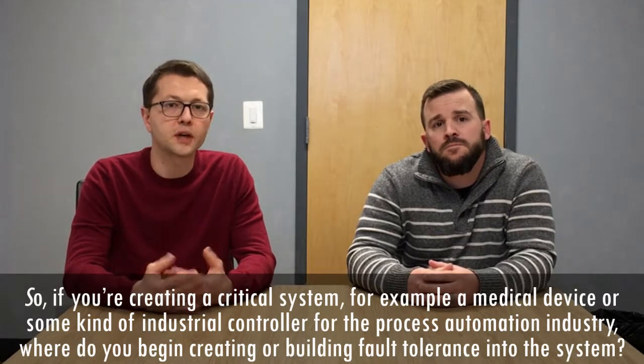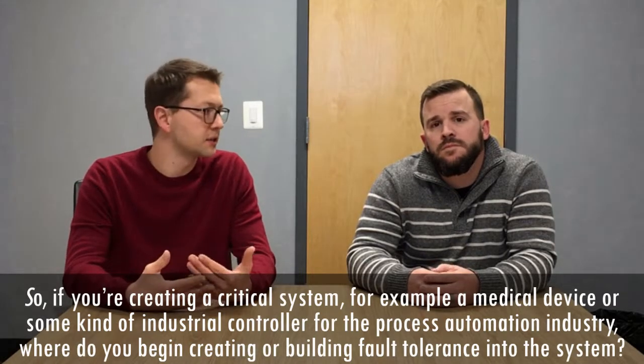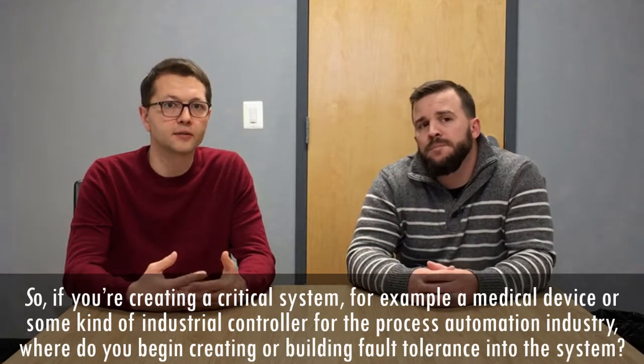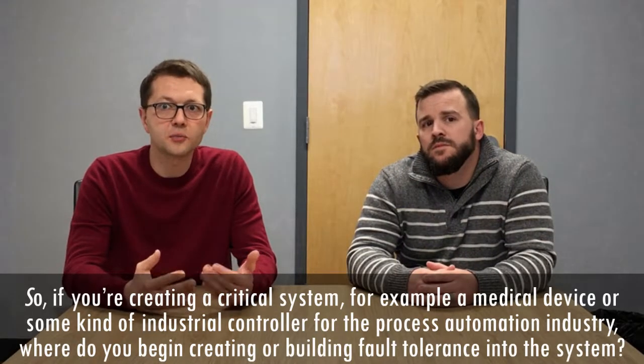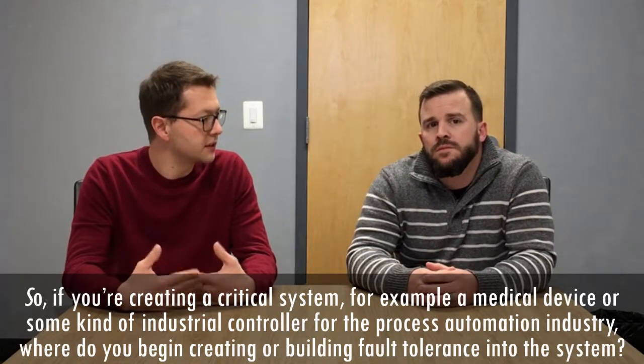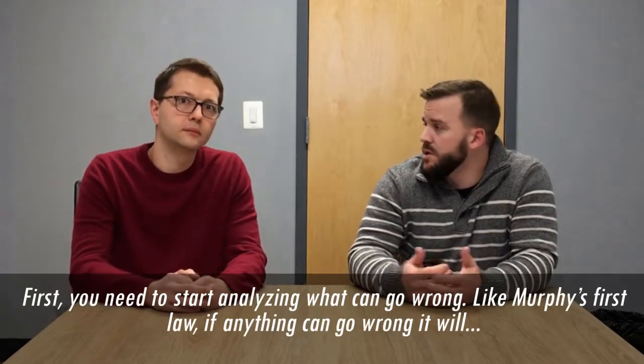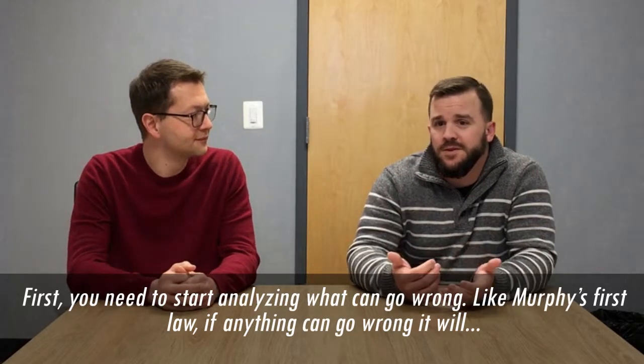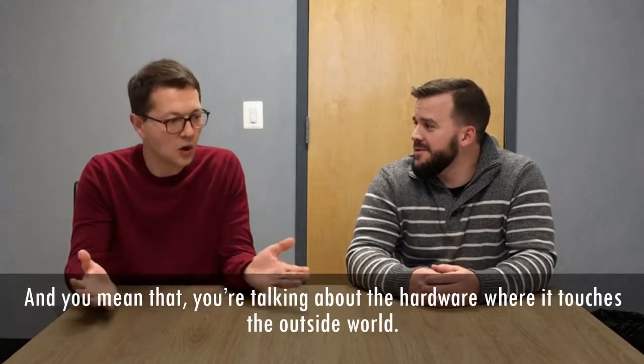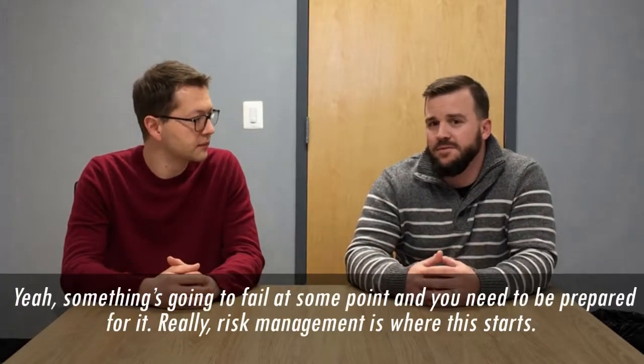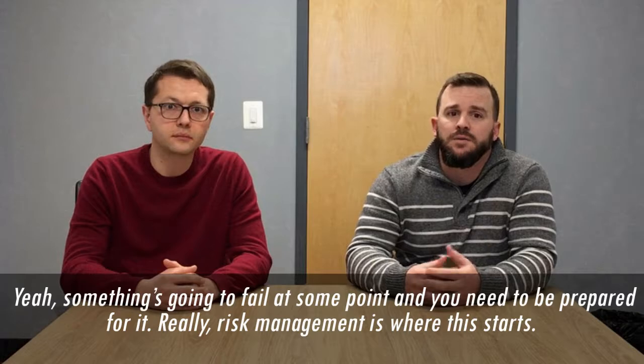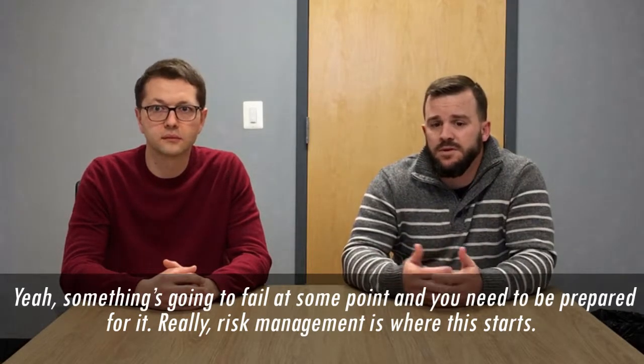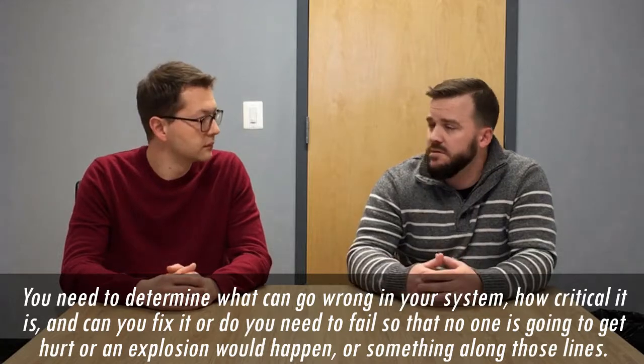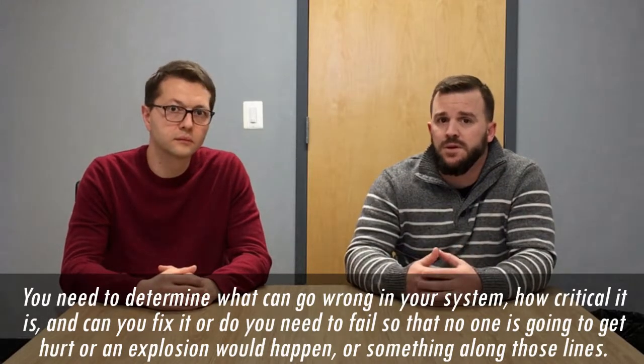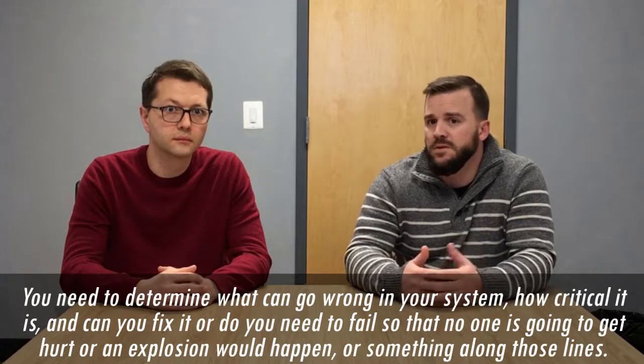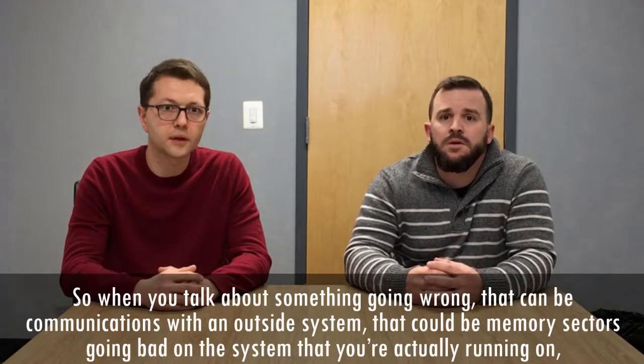Okay, so if you're creating a critical system, for example, a medical device or some kind of industrial controller for the process automation industry, where do you begin building fault tolerance into the system? First, you need to start analyzing what could go wrong. Like Murphy's first law, if anything can go wrong, it will. And you're talking about the hardware and where it touches the outside world. Something's going to fail at some point, and you need to be prepared for it. Really, risk management is where this starts. You need to determine what can go wrong in your system, how critical it is, and can you fix it, or do you need to fail so that no one's going to get hurt or an explosion would happen, or something along those lines.